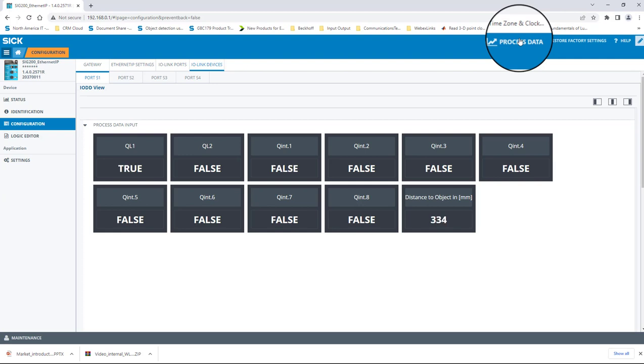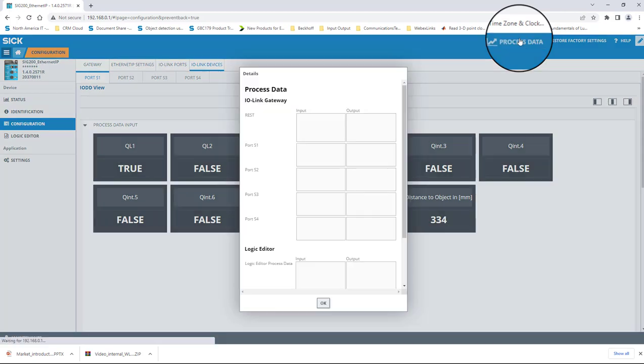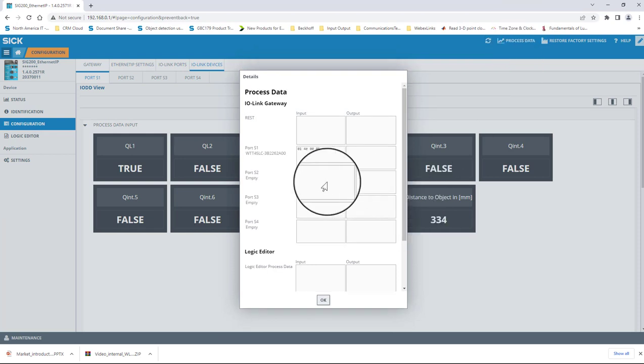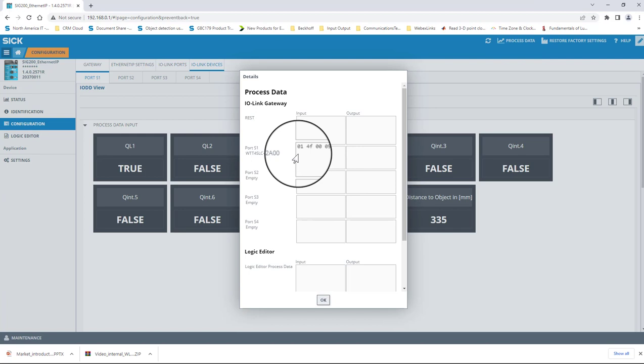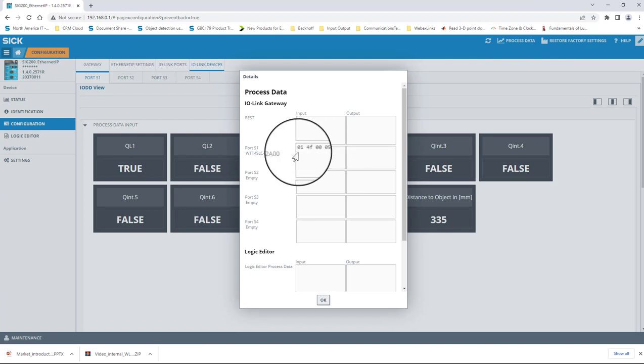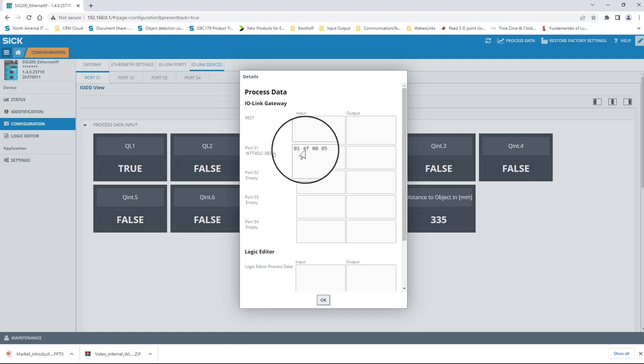If I click on the process data test object in the upper right-hand portion of the page, the window opens up and will display the various data in hex format. Here on port S1, I read 014F0005. This data represents the four bytes of process data that we looked at earlier on the data map.